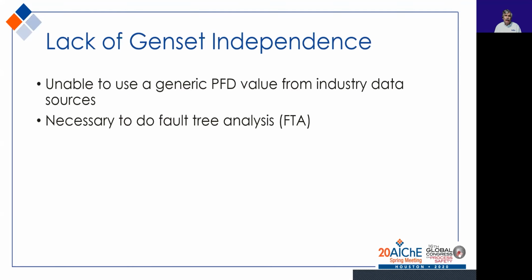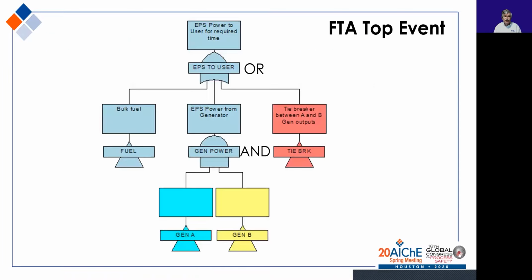Because we have a lack of genset independence, we are unable to use a generic PFD value from industry data. It's necessary to do a fault tree analysis for the EPS to determine what its probability of failure on demand is. So here's the top event for the fault tree. EPS power needs to go to the users for a required length of time. The top event is an OR gate.